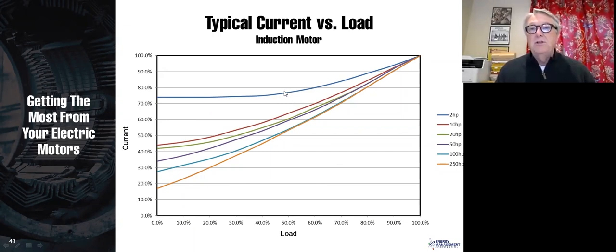Up here, I have a 2 horsepower motor. 2 horsepower motors, I remember looking at one, it said ultra high efficiency motor. Actually, that one was like a 1/4 horsepower. And the efficiency was like 46%. And they also have very high starting current. So if you get into what I would call these little peanut motors, even at no load, you can have very high currents into them.